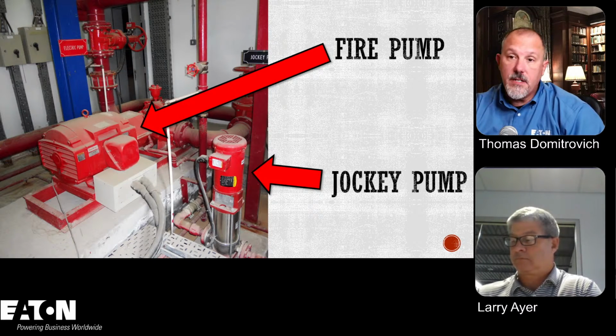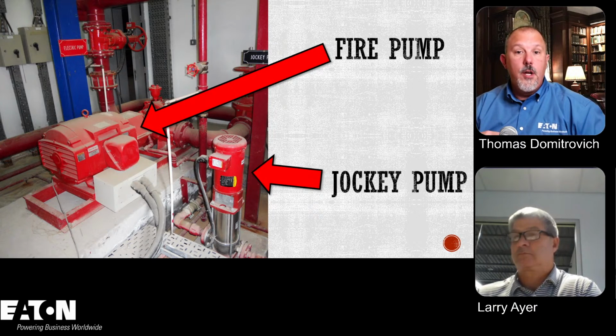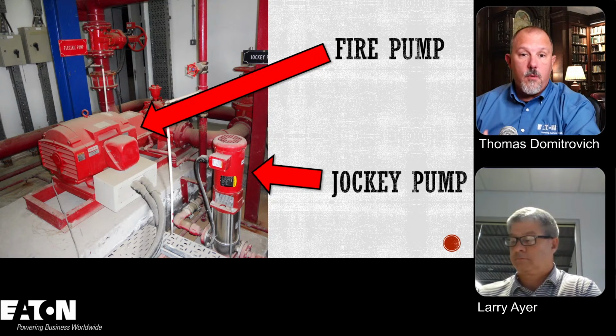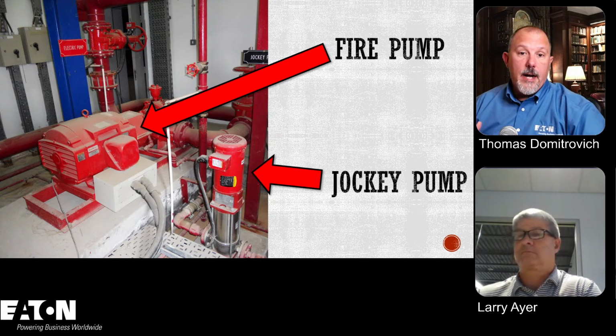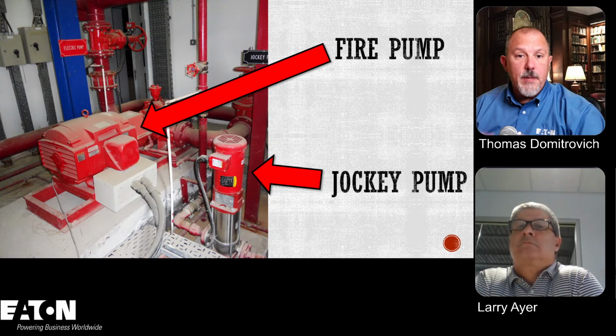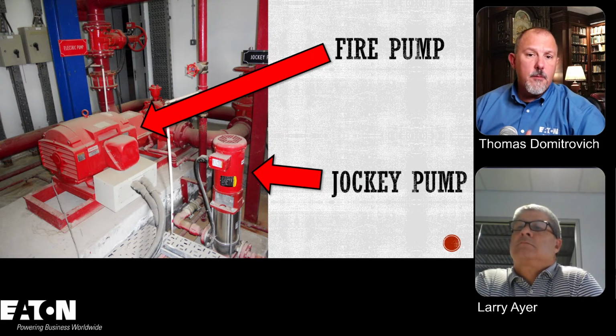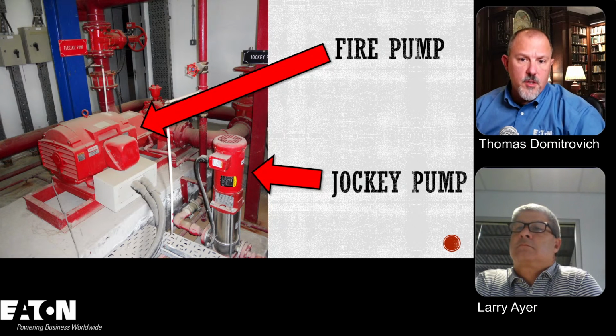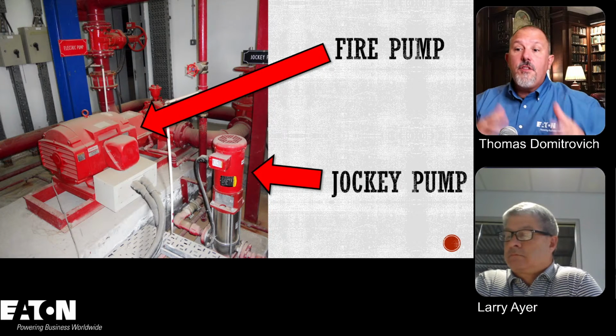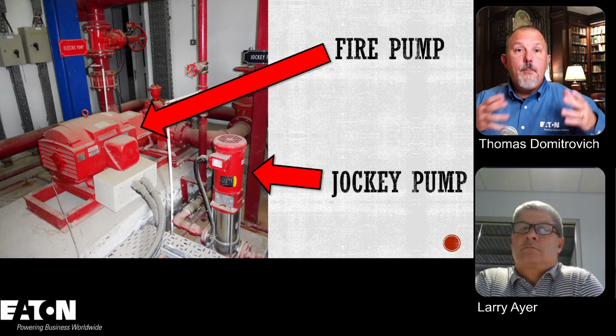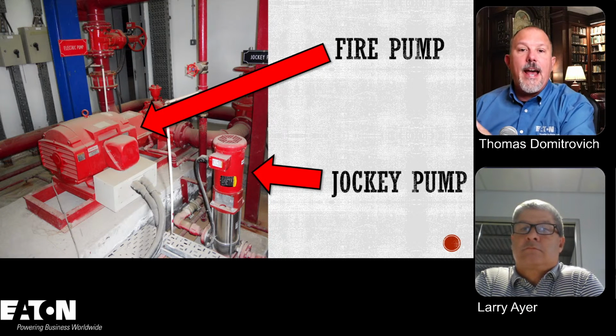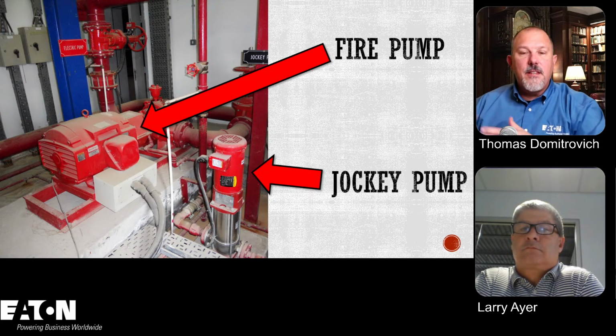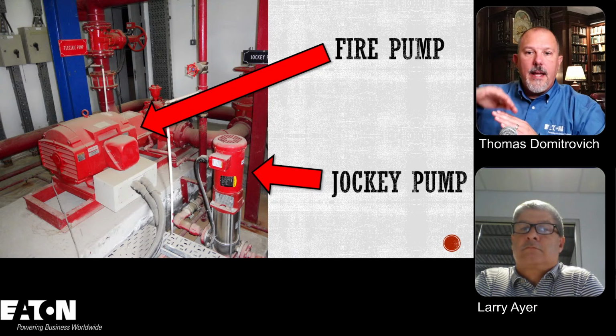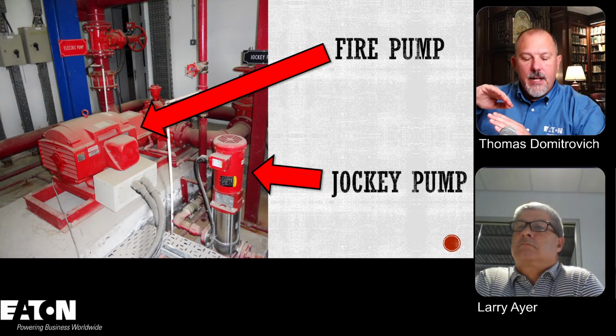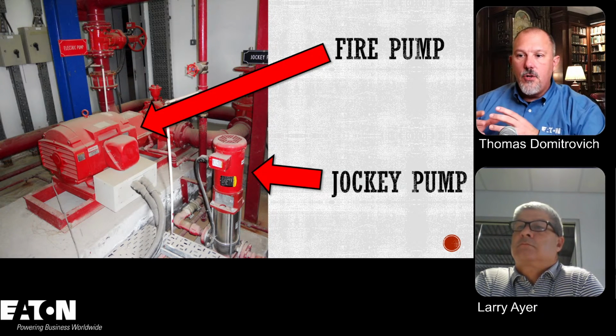Now I don't have a copy of that. I can't tell you some of the specific requirements around fire pump motors. I'm sure there's probably special labeling requirements. There might be other requirements from a performance perspective. To your point, Larry, when I pick a motor for a specific application, I'm looking at the design types because I want to know when I hit the peak, my torque and all of that good stuff. So this is a specific load from a fire pump perspective.